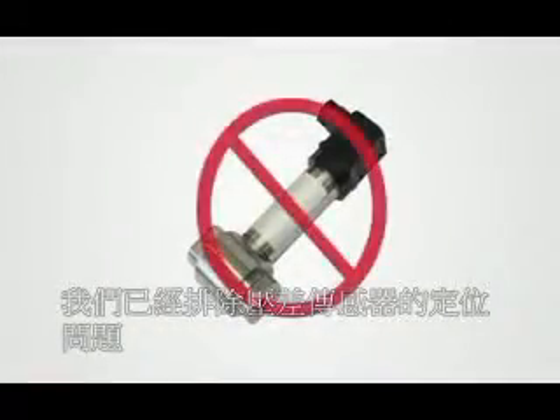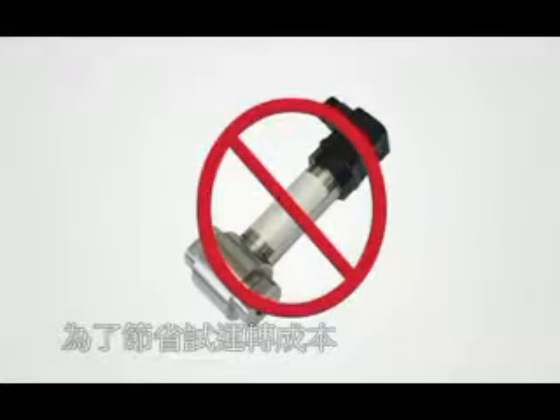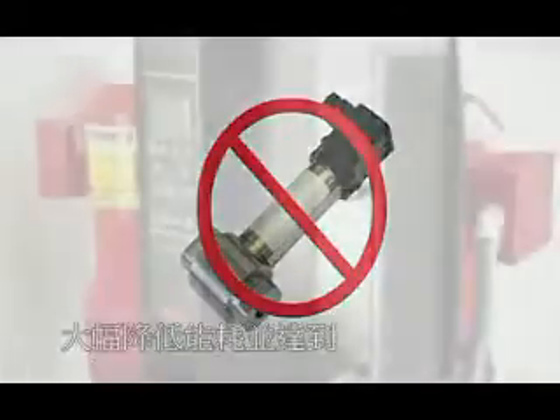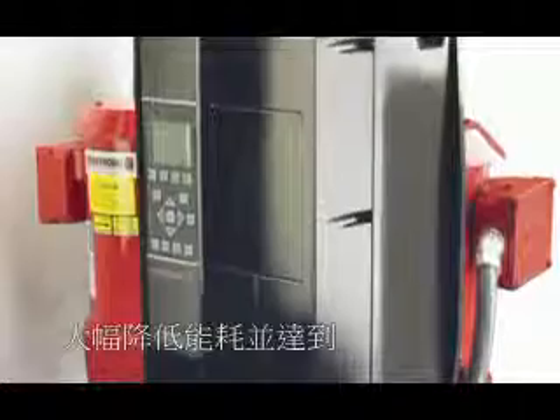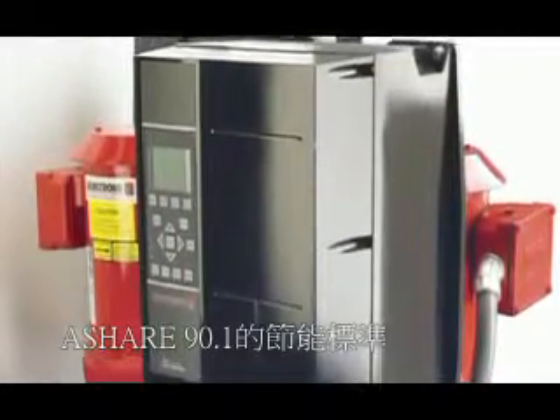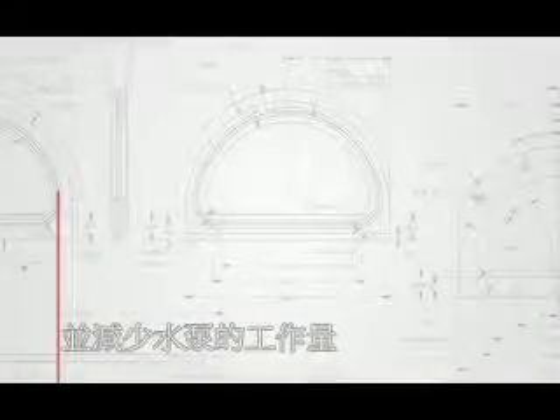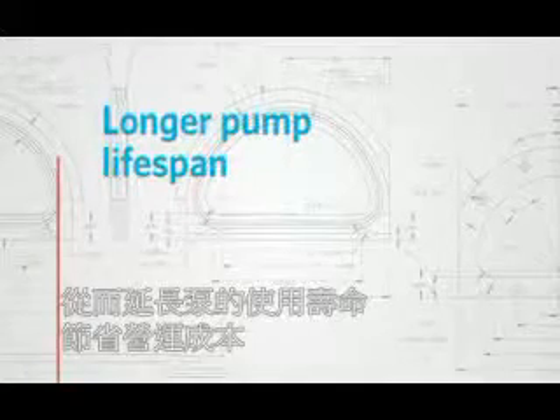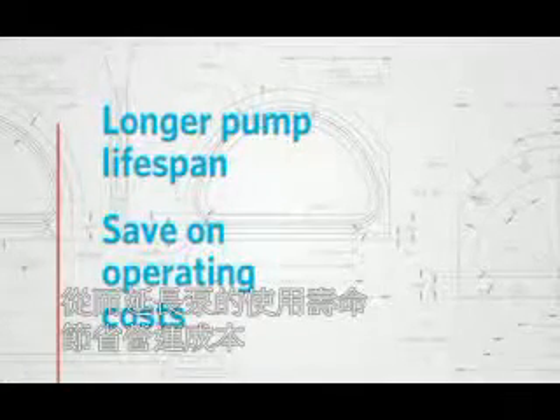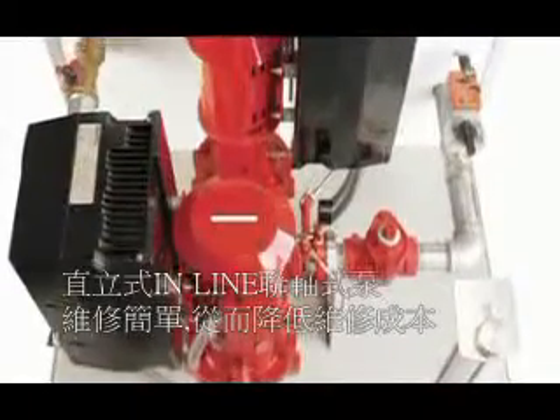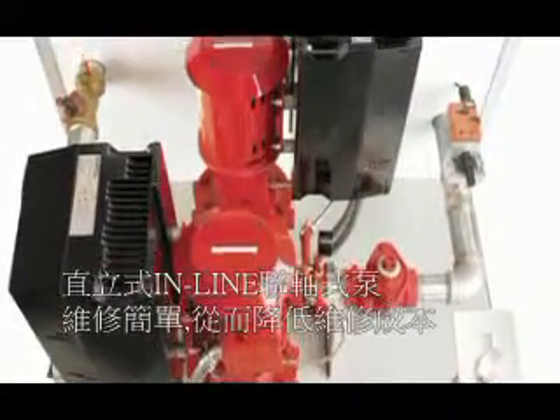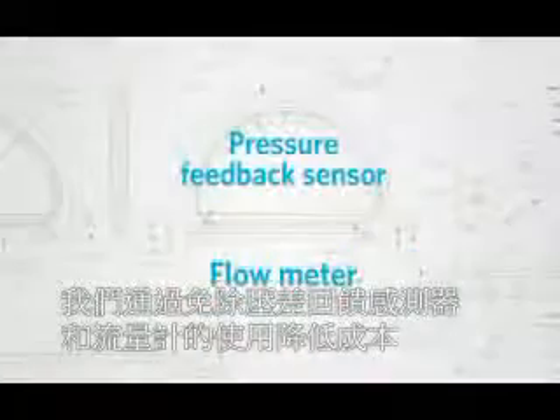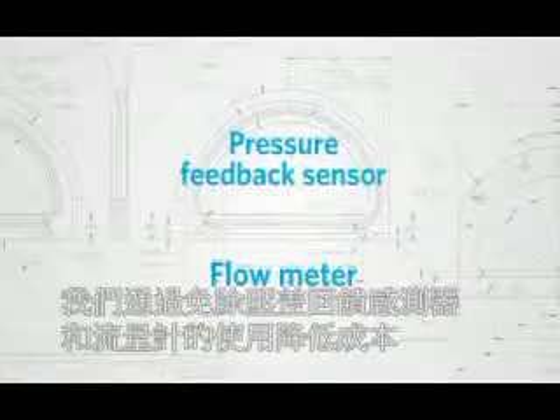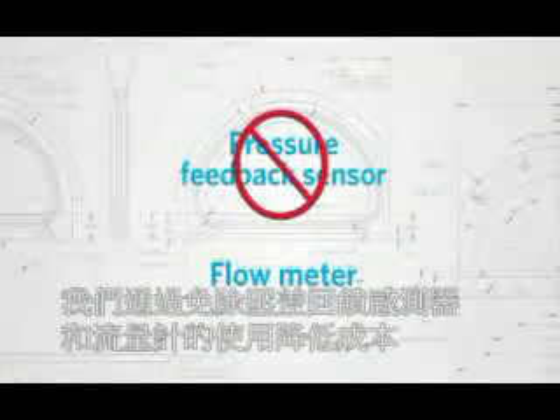Because we have eliminated pressure sensor positioning issues, you save on commissioning costs. Impressive energy reductions meeting and exceeding ASHRAE 90.1 and reduced pump work result in a potentially longer pump lifespan. That allows you to save on operating costs. Vertical inline split coupled pumps are easily serviced, allowing for reduced maintenance costs. And we have cut back on capital costs by eliminating a pressure feedback sensor and a flow meter.